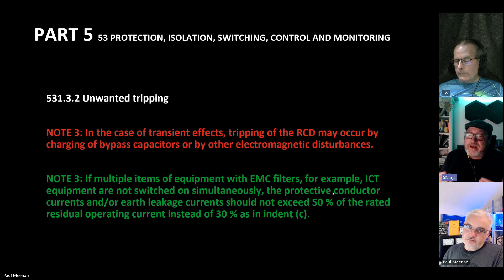I can kind of understand it though, because in the 2396 project that we have right now, which was a library for last year, there are guys putting so many sockets and so many circuits because they'd have one or two laptops, and they go, well, a laptop would have this kind of leakage, so we can only put two or three sockets per RCD. Yep. But because the intent is 9 milliamps, what they're saying here is really that we're talking about a sudden load or simultaneous load pushing to 9 only. But if things are over a period of time, we can go up to half I delta n, which I think is where 7909 goes to as well, 50%.